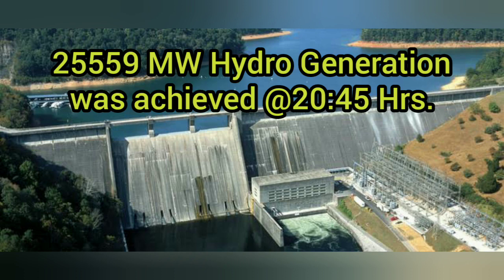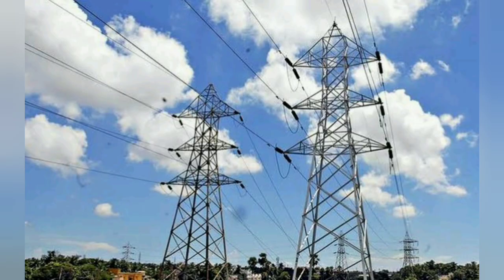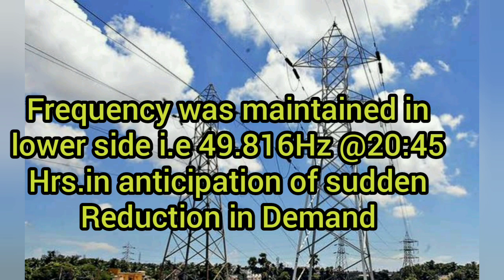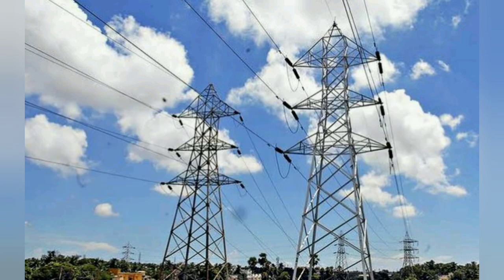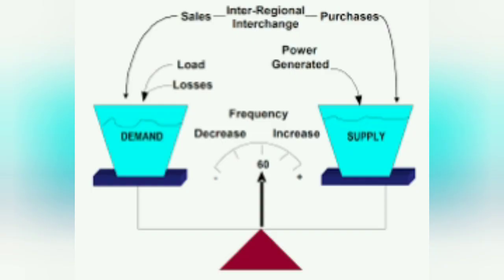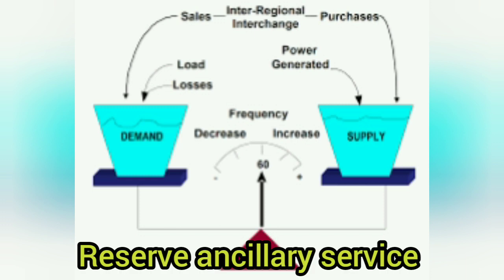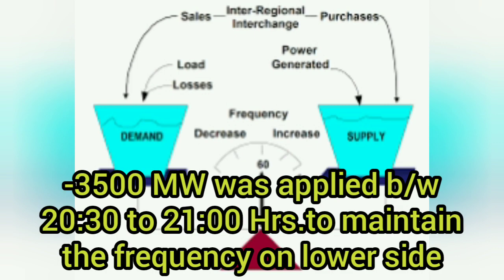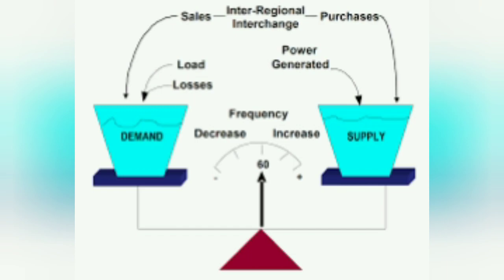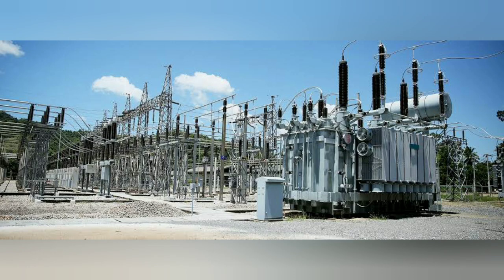Hydro generation of 25,559 megawatt was achieved at 2045 hours. In anticipation of high frequency at the time of sudden reduction in demand, the frequency was maintained on the lower side, that is, it was maintained at 49.816 Hz at 8:45 p.m. before the start of the event. Total reserve regulation ancillary services down of 3500 megawatt was applied between 2030 and 21 hours to maintain the frequency on the lower side of the IEGC band.